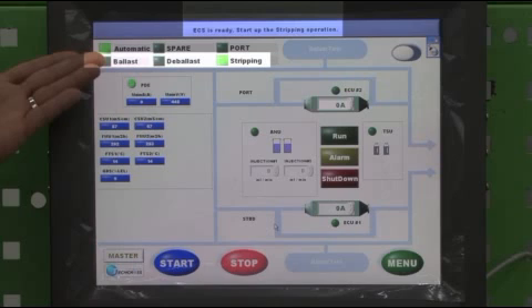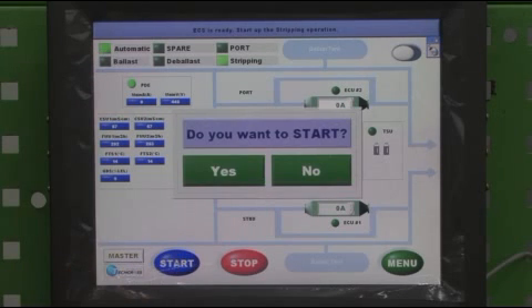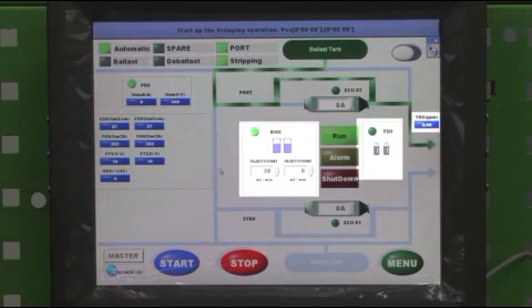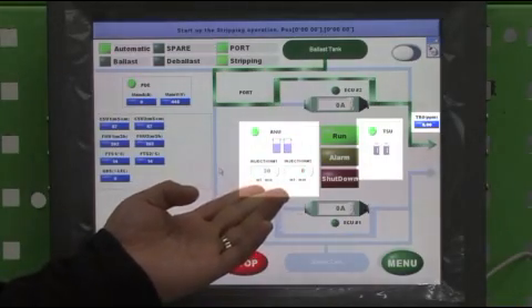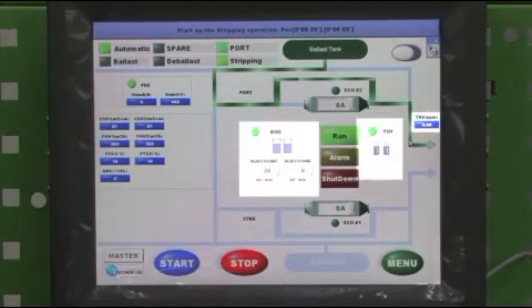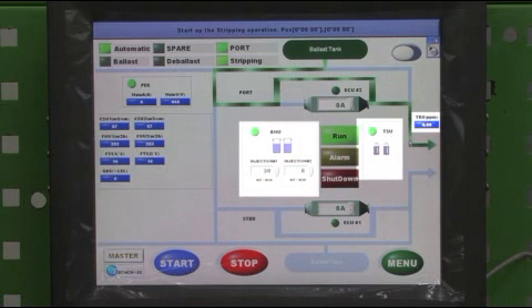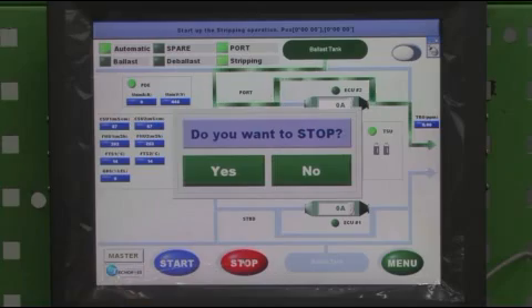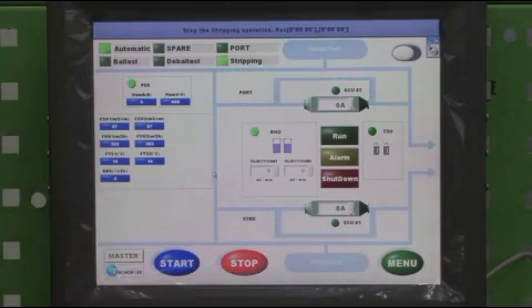Check the top message and mode display to see if all the stripping operation requirements are fulfilled. Ensure that the top message says, ECS is ready, and start up the stripping operation. Step 3. Click the Start button on the HMI screen to operate ECS. Step 4. Ensure that the ECU value and TRO value are displayed immediately after operating ECS. Alarm or shutdown should not occur during normal operation. Step 5. Close the stripping valve first to stop the stripping operation. Click the Stop button on the HMI screen to stop ECS operation.